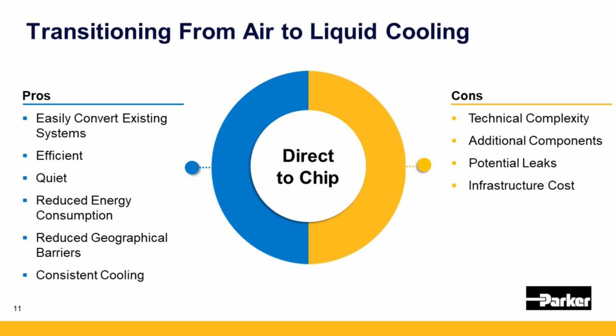Obviously, what everybody is most worried about with a lot of liquid cooling is the potential for leaks, which the system design needs to address directly to avoid failures you might otherwise experience. Then there's cost - the infrastructure cost is more than an air-cooled system, but as Liana said, the cooling costs you pay throughout the life of the product make the total cost of ownership significantly less for these liquid-cooled solutions, in this case for direct-to-chip.